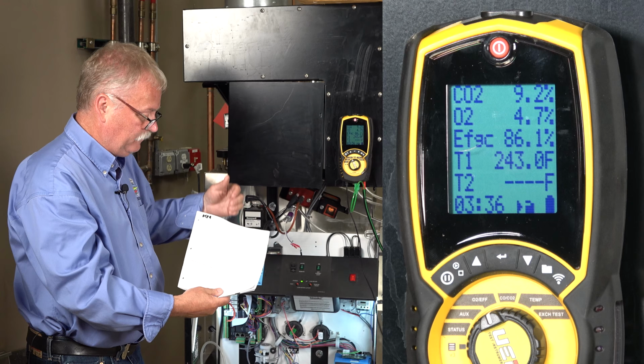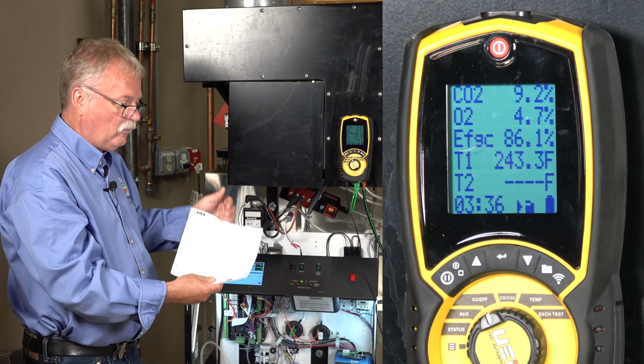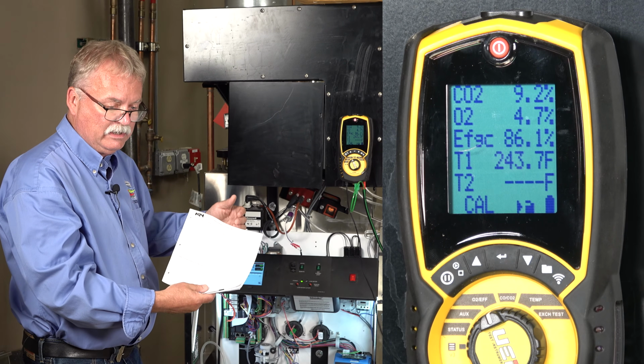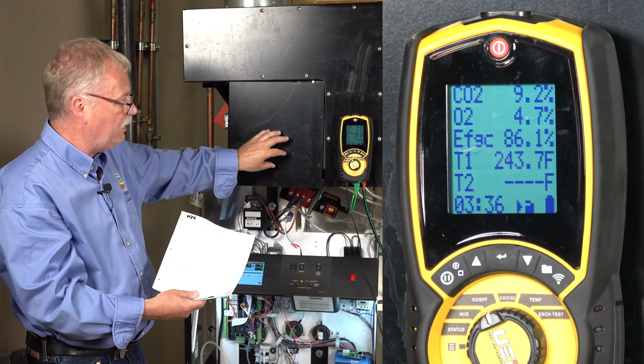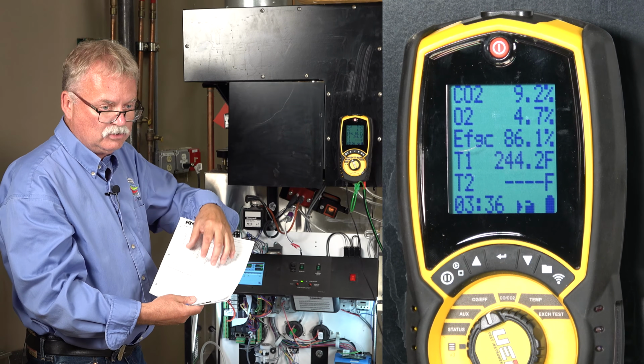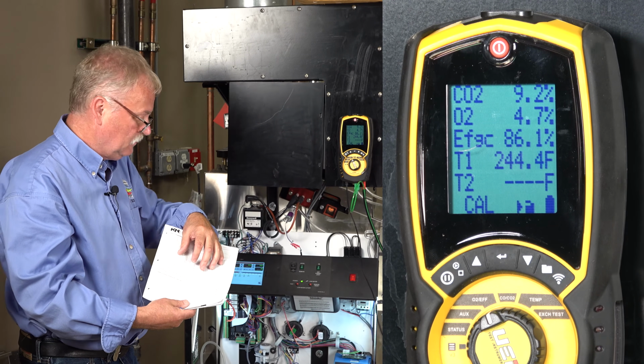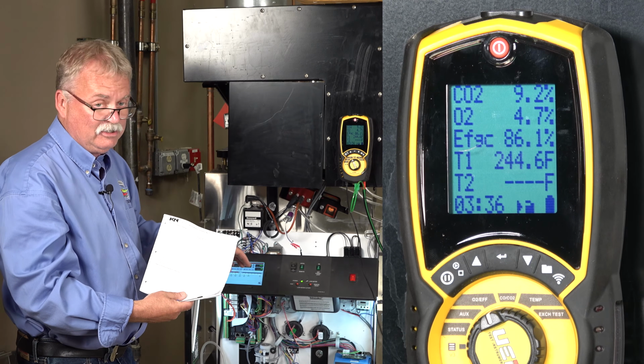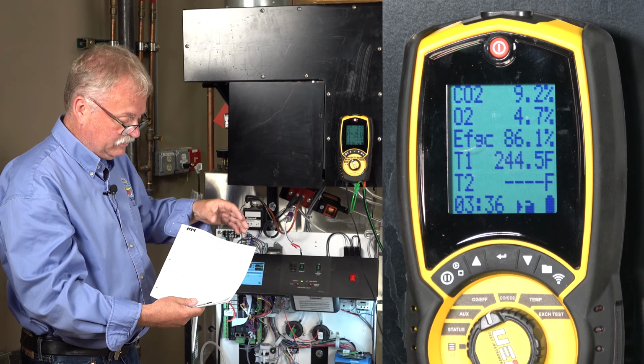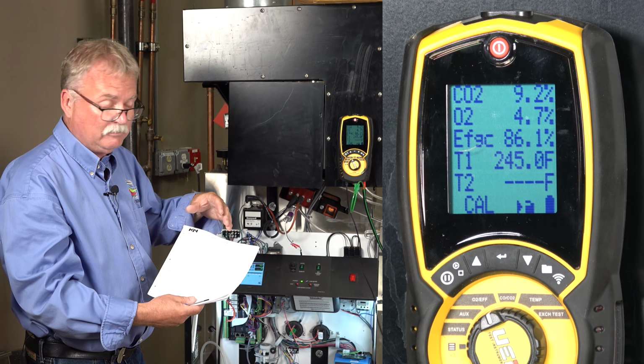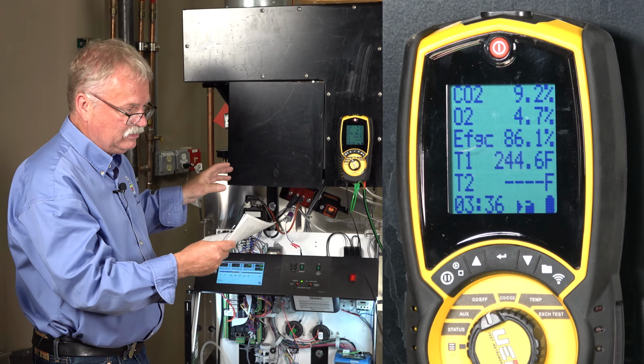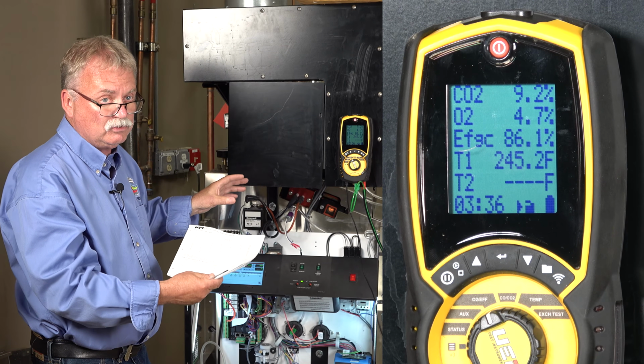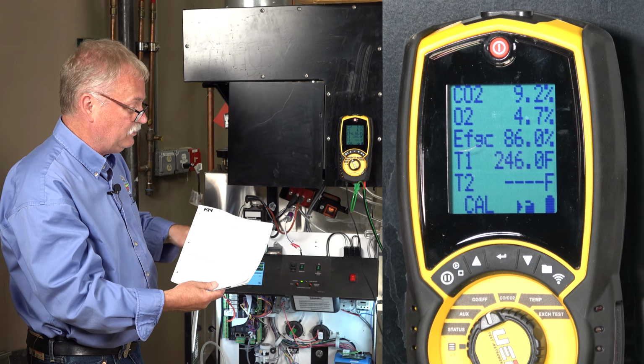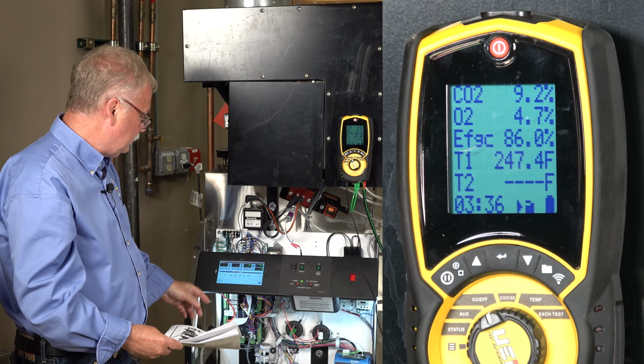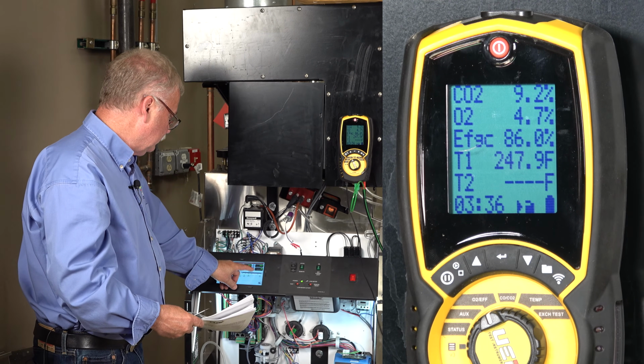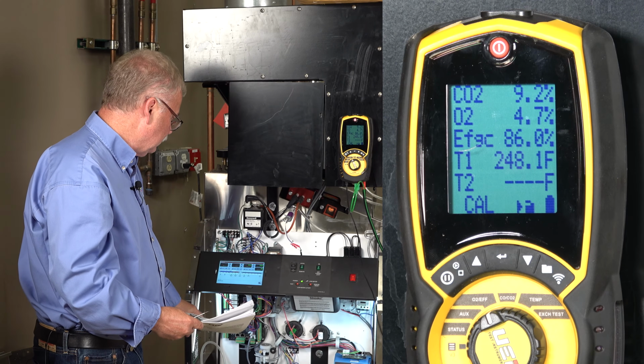So basically, you get the manual for that boiler. If you don't have it, go on the internet and get it for that year or whatever, because these numbers do change. I've been working with this boiler for about 10 years now, and the numbers have actually been dropping. So they've been improving the efficiency of the heat exchanger and other stuff you have no control over. So they do change over time. But what I would do at this point, since we're satisfied with this number, is lock that in.